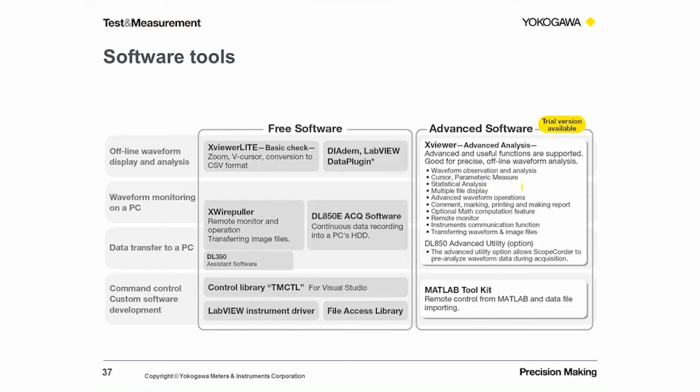because it is possible to export data from the unit in our WDF format, which of course means that the data is in its minimal form. If you want to convert to a CSV, it expands the data, of course, and means the file is much heavier, much bigger, and of course that's easier to do in the PC, although it is possible to export as CSV from the instrument.